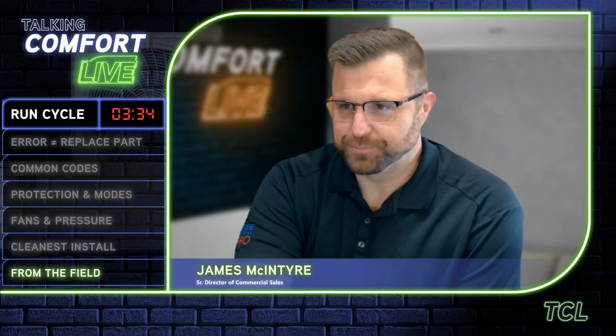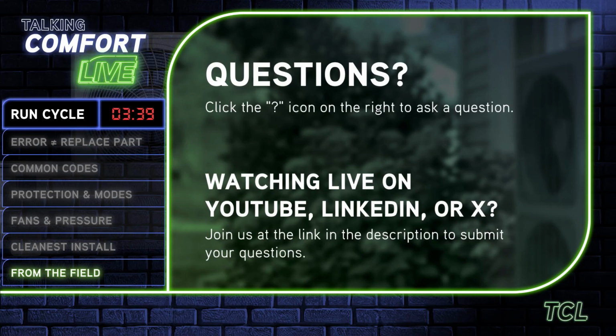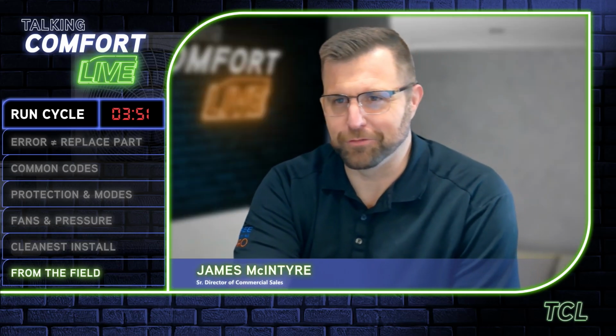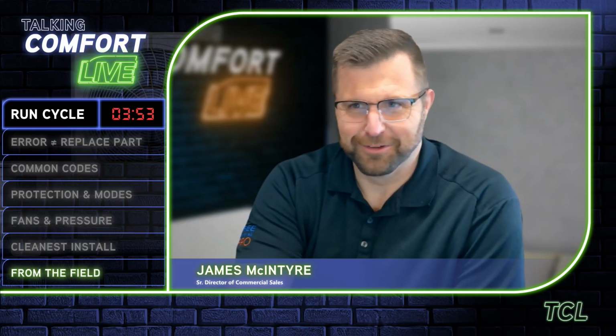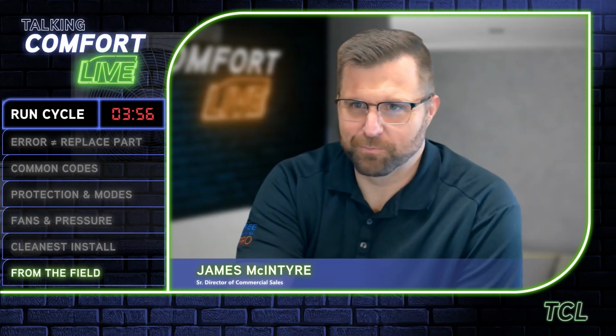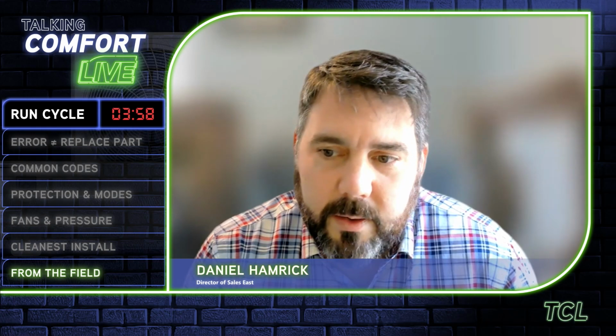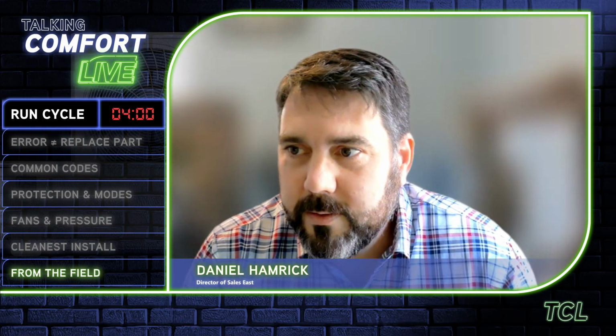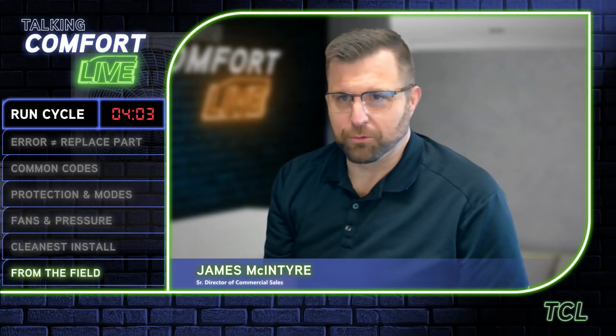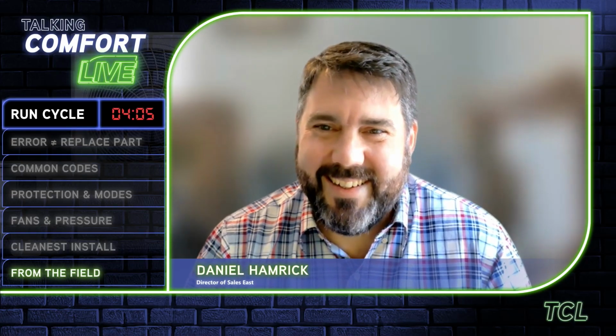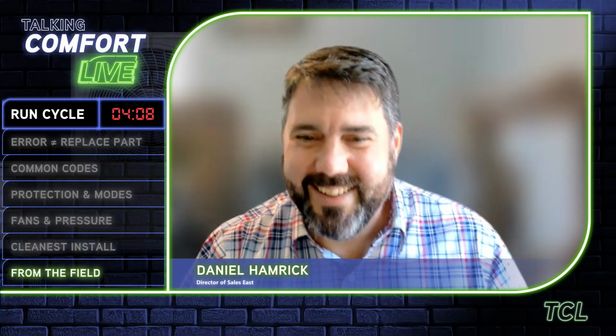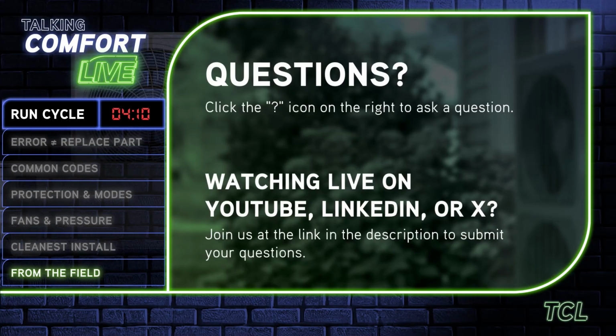So, all right, looks like we got one more input. We got Craig says, I had a problem when the homeowner cut all of the trees down around the house and increased the sun load. The unit would not keep up after. What do you do to fix that? Plant some trees. A bigger unit, but don't increase the ductwork. No, you increase the airflow and then try to get your delta right, somehow increasing the capacity.